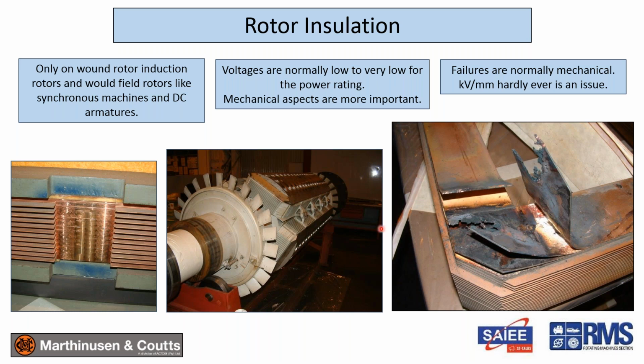And the reason it's overkill is for mechanical considerations. In the center is a salient pole synchronous machine. You can see V blocks in here. They hold the coil in due to the tangential component of centrifugal force. So even though the voltage is low, you have to consider very thick insulation. And the slide on the photo on the left shows that very clearly. The inter-turn insulation you can hardly see, yet the insulation that insulates the whole coil from the rotor body is very, very thick for mechanical considerations.